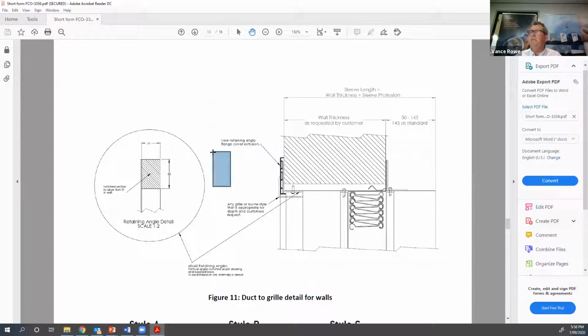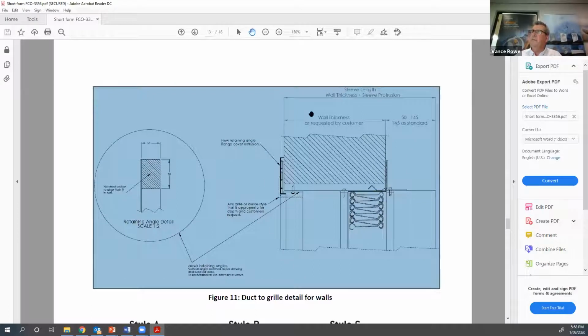Yeah, go for it. So this is straight out of our short form assessment report. You'll see that detail there that I'm circling. I've highlighted it now in blue. So that is the detail that we would recommend in that sort of situation. You've got your grill or your louver on the outside there. We actually have an aluminium extrusion that covers the fixing angle. That angle is reversed, so that the mounting sleeve for the fire damper doesn't actually protrude out where I've got my little hand in the drawing there. And then the fire damper sleeve goes through the wall.